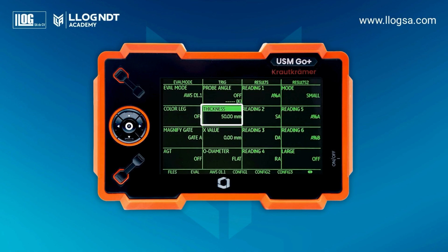In the thickness option, we define the thickness of the part to be inspected. It is also possible to enter the X value, which indicates the distance from the probe index point to the front edge of the probe or wedge. If the inspection surface is flat and parallel, we select the Flat option. For curved surfaces, we can enter the outer diameter of the part, and the instrument will automatically correct the beam path distance and depth.